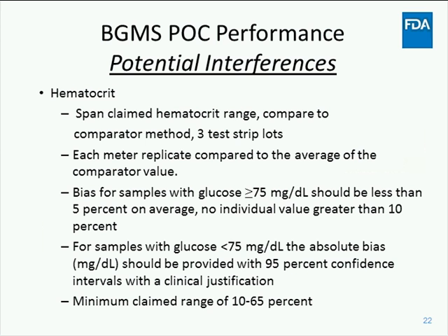It is well known that hematocrit levels can significantly affect blood glucose meter readings, with a significant positive meter bias at low hematocrit and a significant negative bias at higher hematocrit concentrations. Due to this known interference, a separate hematocrit study should be performed with these devices, as is currently done. The blood samples used should reasonably span the glucose measuring range and the hematocrit range. The meter results should be compared to a comparator method by comparing each meter replicate to the average of the comparator value. The bias for samples with glucose concentrations greater than 75 should be less than 5% on average, with no individual value greater than 10%. For samples with glucose less than 75, the absolute bias should be provided along with 95% confidence intervals and a clinical justification.